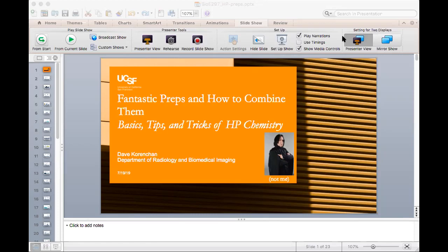Use a larger tip angle. Sample a little more heavily on it. This is a great way of getting preliminary data for a compound, because if you see signal, especially when it's not C13 enriched, that's a great sign that this will work. You can also measure the T1s. So you get those two parameters, and you can very quickly have a sense of how well this compound is going to work.